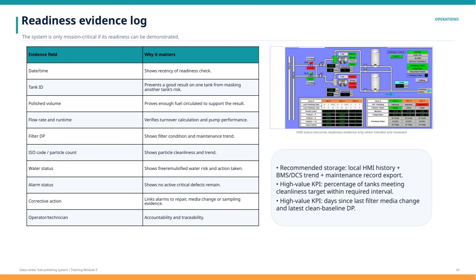Flow rate and runtime verify that the turnover calculations and pump performance are accurate. The filter differential pressure, or filter DP, gives insight into the filter's condition and helps us monitor maintenance trends. ISO code, or particle count, records track particle cleanliness over time, which is critical for fuel quality. Water status indicates potential risks from free or emulsified water and shows what actions have been taken. Alarm status confirms that no critical defects remain active, and corrective action records link any alarms to the necessary repairs, media changes, or sampling evidence. Finally, the operator or technician's name provides accountability and traceability, ensuring responsibility is clear.